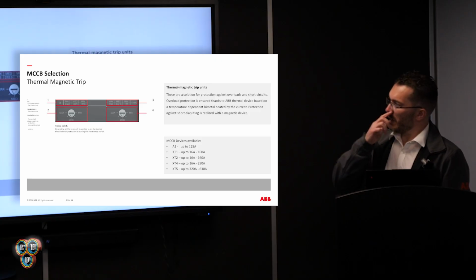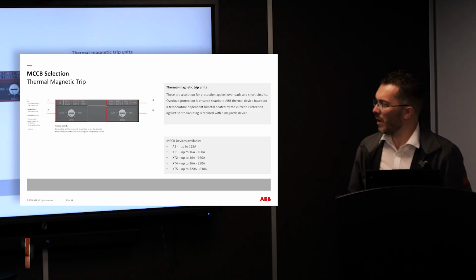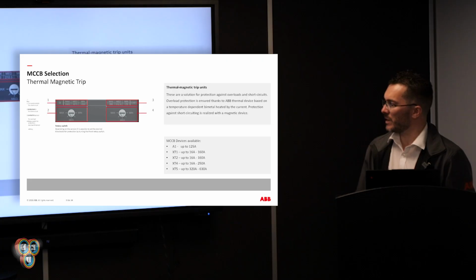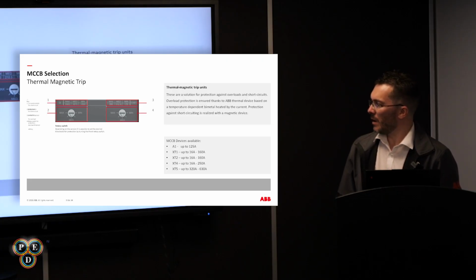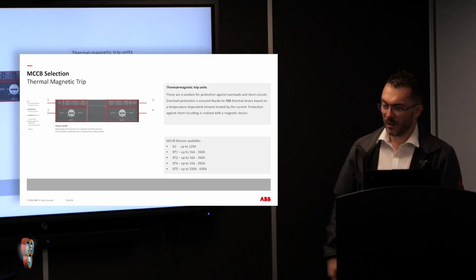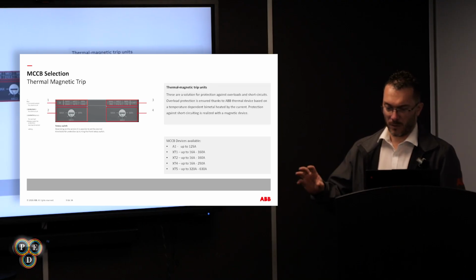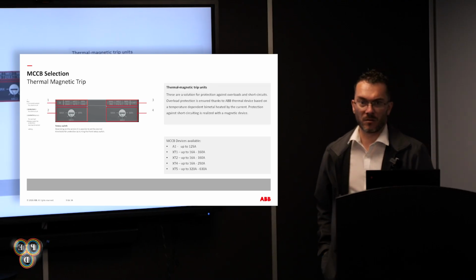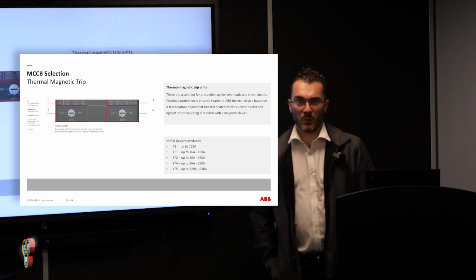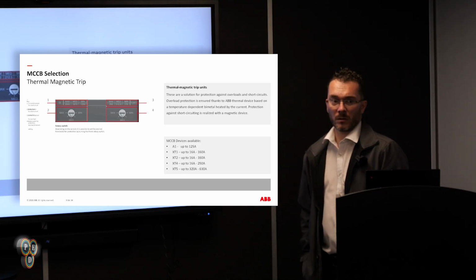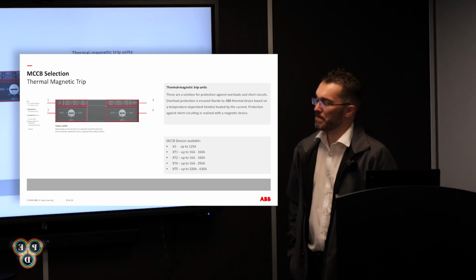Selecting some settings on the thermal mag: up to 125 amp in the single phase, 160 amp in the XT1 and the XT2, 250 amp in the XT4. But one of the main things for this panel board is we can now go up to a 630 amp outgoing way, which we never used to be able to on our old R2 panel board. The maximum was 250 amp.